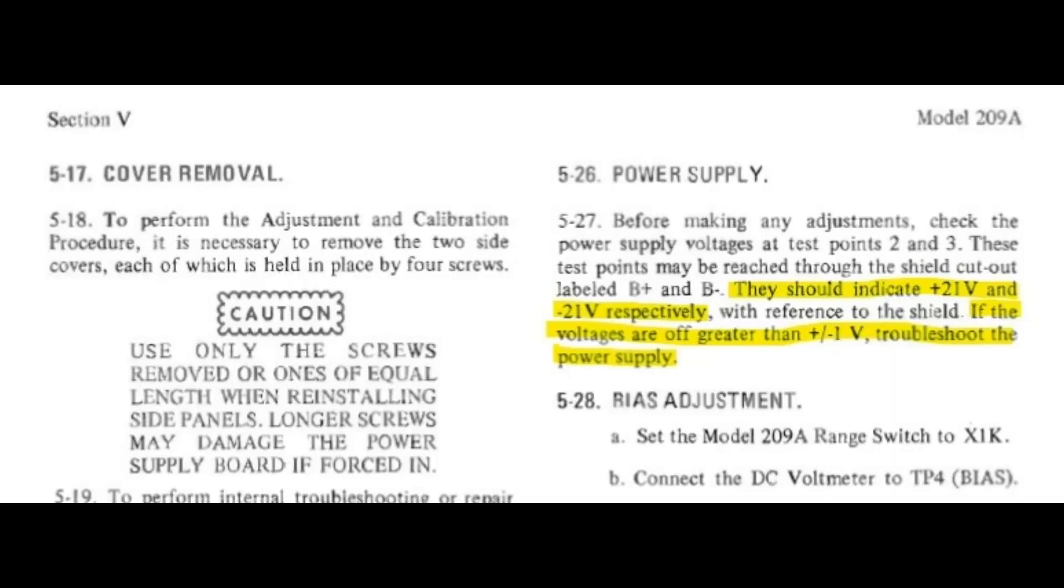According to the HP manual, these voltages should be a nominal plus or minus 21 volts DC with a tolerance of plus or minus 1 VDC. Clearly, there is an issue here.